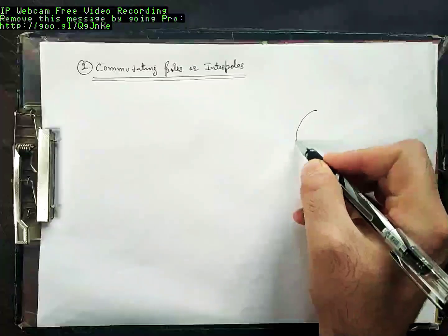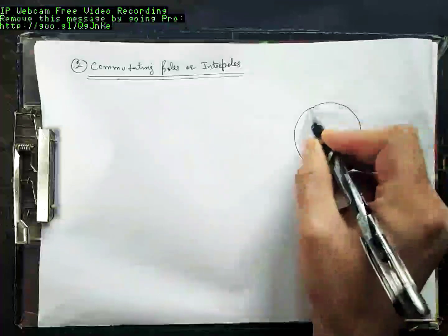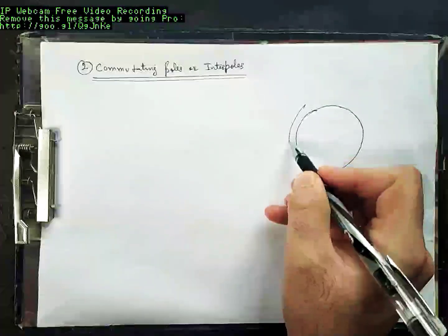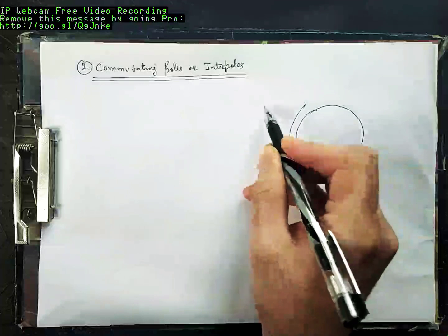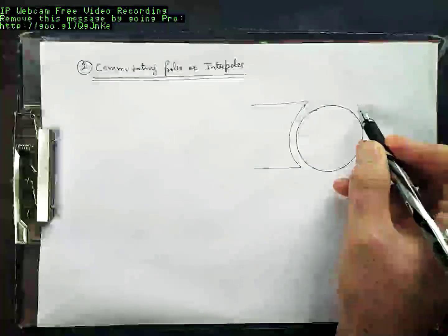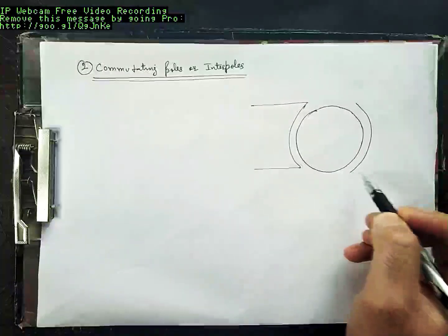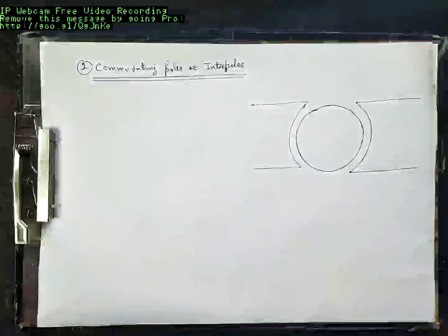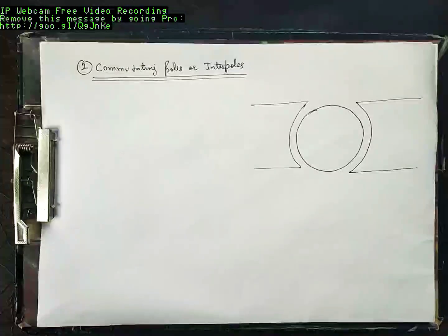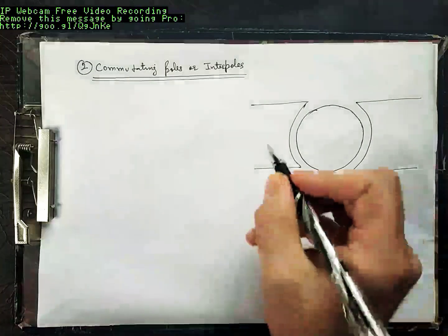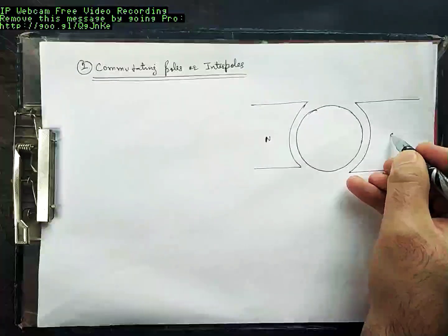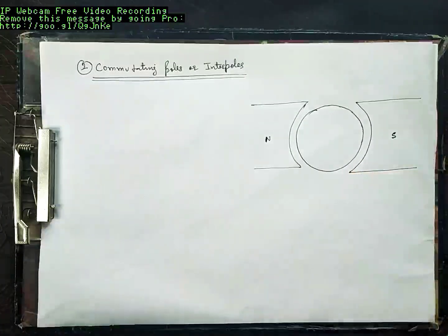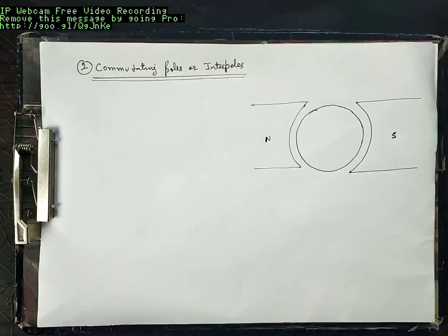In the last few lectures, we discussed that in real DC machines, whenever there is a current flow through the armature, it produces a field of its own, which tends to distort the main magnetic field in the machine, known as armature reaction. Because of the armature reaction, there are two effects. One is the shifting of magnetic neutral plane, and second is the flux weakening.